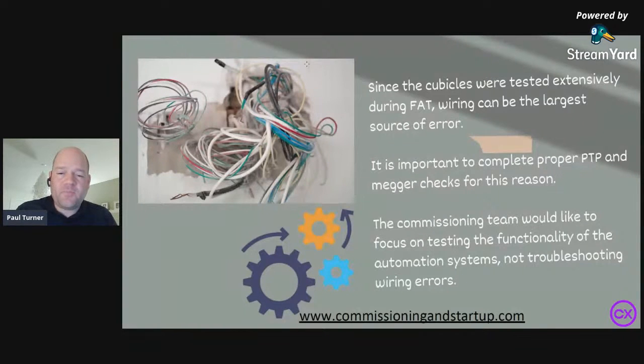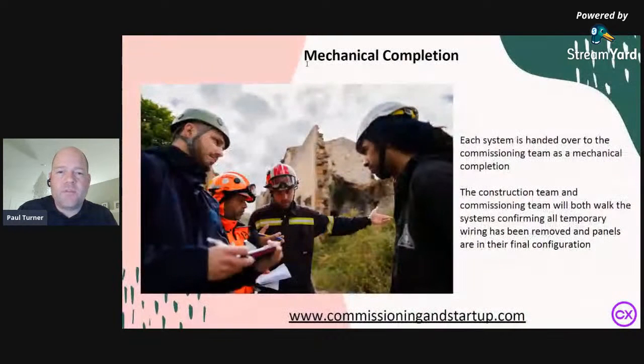As a commissioning team, we certainly want to be testing the actual functionality of the plant systems. We don't necessarily want to be troubleshooting all the wiring errors. Of course, there's always wiring errors that pop up, and the odd one isn't a big deal. If you've got a rolled wire and you need to flip it, that's not that big a deal. But if the commissioning team instead is spending their time troubleshooting multitudes of cable errors, that's not entirely productive. So there does need to be a proper upfront process defined in construction ITPs to do all the point-to-point and megger checks of all the cables.